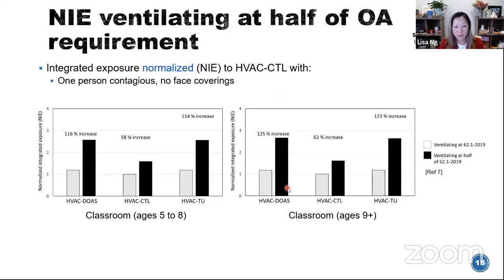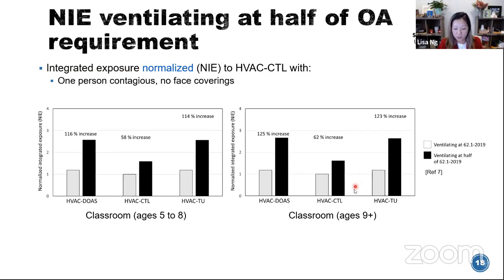Schools can be under-ventilated based on published studies. We simulated the three systems with almost half the ventilation rate and found increases of over 100% — meaning the integrated exposure doubled — for the DOAS and terminal unit systems. For the central system, the increase was 58 to 62% across the two classrooms. That's because the central system has a MERV 8 filter, whereas the DOAS and terminal unit systems use MERV 6 filters as their base operation.